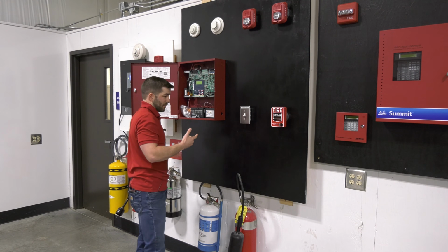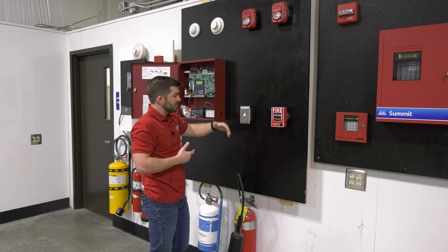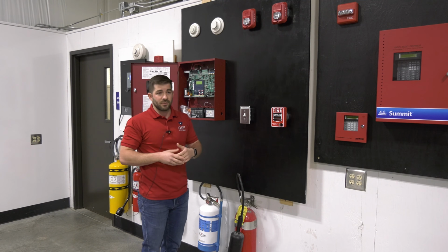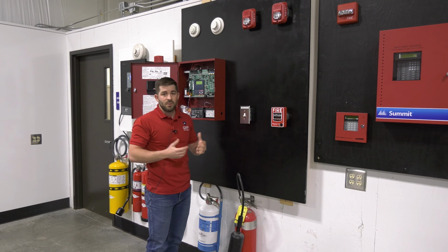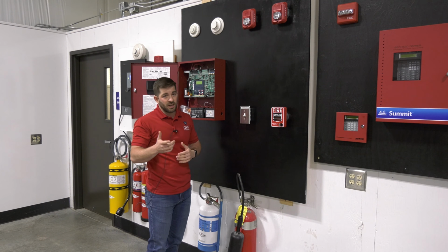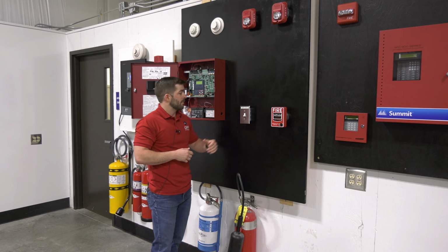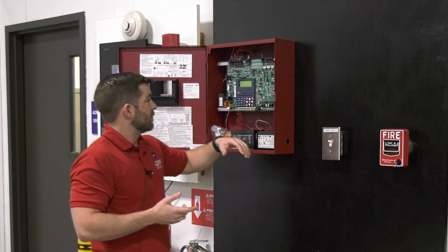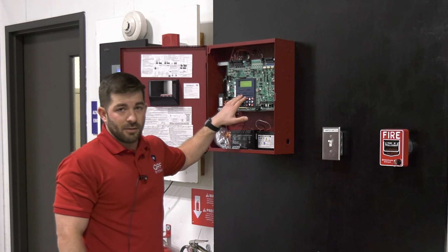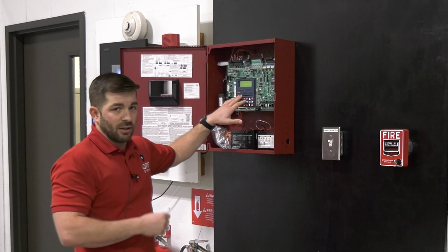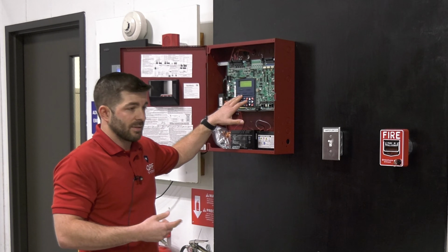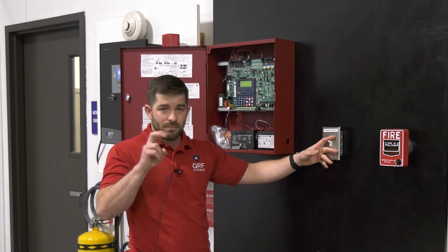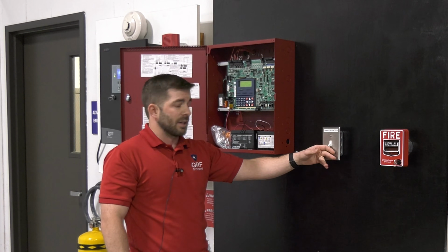Now, supervisory. I have a little switch right here to represent a supervisory, whether it be a control valve on a riser, phase reversal, power loss on a pump controller, even your duct detectors if your AHJ allows you to program those as supervisory. Now, it takes up to 90 seconds. Now you see, this LED is lit up for supervisory. That tone, it's in yellow, but it's faster than what the trouble was. It has to be distinct. Now, I'm returning it back to normal, and it clears.